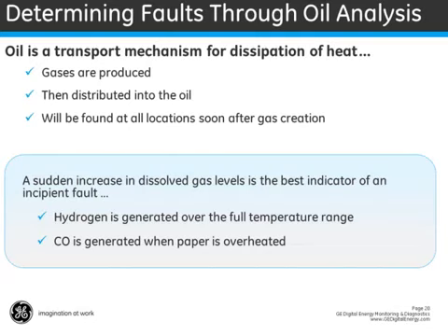So gases are produced due to normal aging, and this is well known. However, the type of gases and the rates at which they are produced can be directly related to the stress condition the equipment is suffering under. Gases are generated at a rate associated with the severity of the stress condition. But in addition, different gases are produced at different rates under a given category of stress.